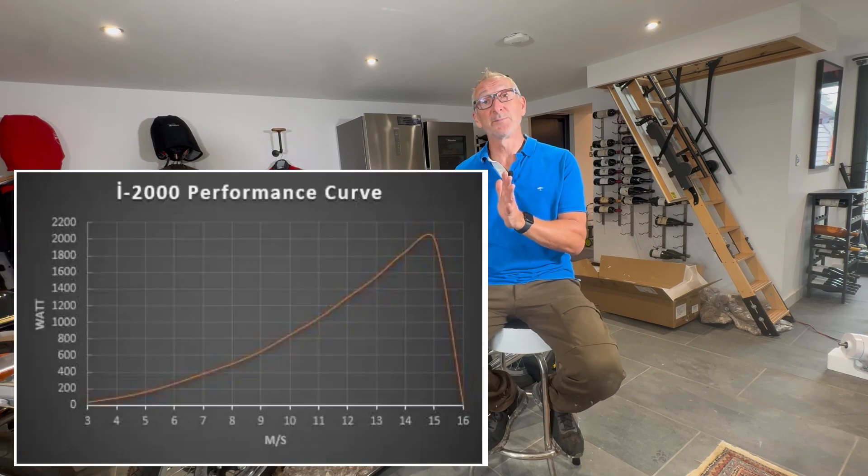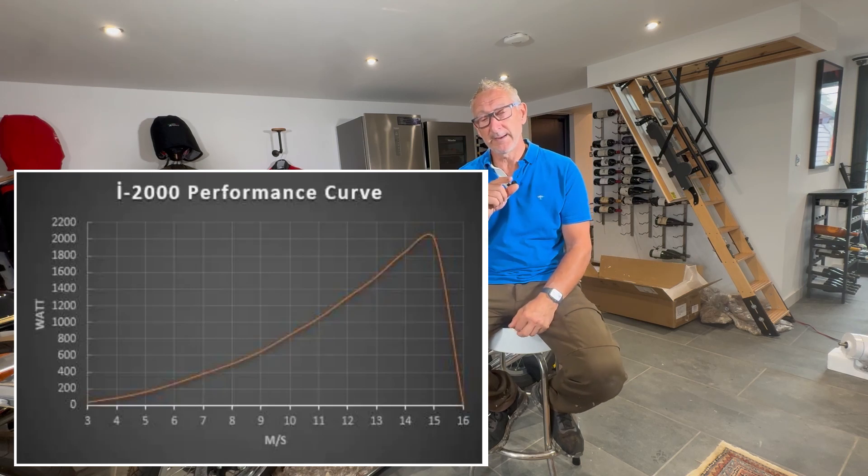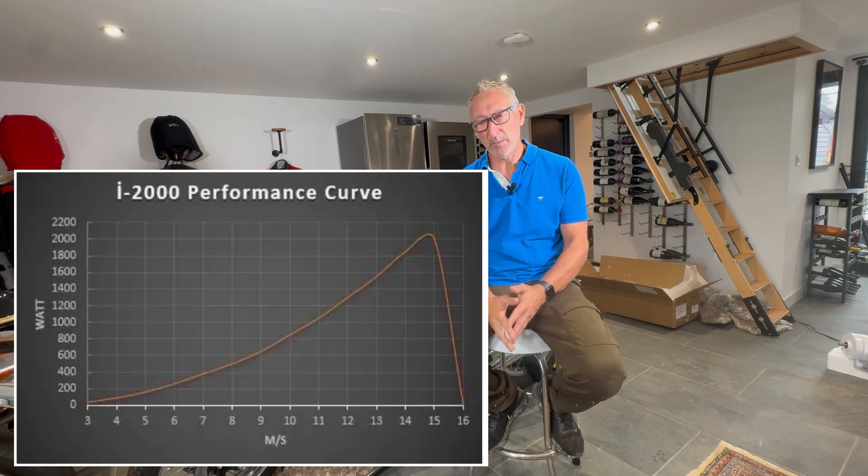What you're waiting for is what the manufacturers call the cut-in wind speed — the wind speed at which you start to get, in my case, the 24 volts required and you start producing some power. If we take a quick look at the iSTA Breeze manufacturer's performance chart, you'll see that the cut-in wind speed is three meters per second. So it's showing something should be producing at three, and from that point on you start producing power.